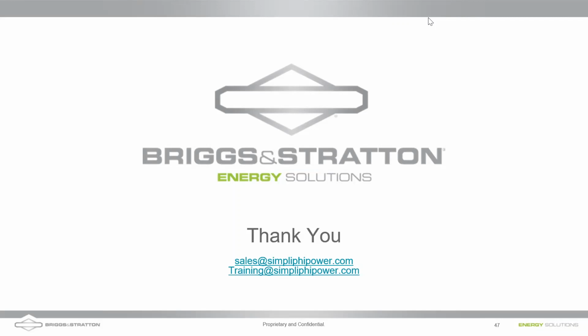Can the generator be used on top of, or in addition to, the batteries, and how is this managed? Yeah, the generator can definitely be used at the same time as the batteries. So if you've got that generator going into the gen input on the inverter, you can use the generator to charge the batteries while you're powering a load. You can use the generator to power a load, etc. You can use solar, gen, and grid all at the same time if that's what you need to power the load. It's going to be able to take in all these inputs together.